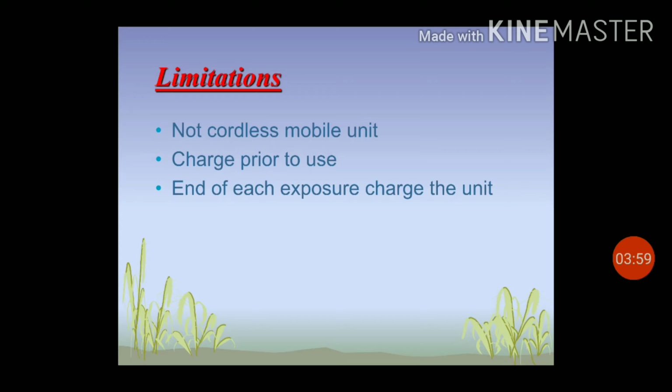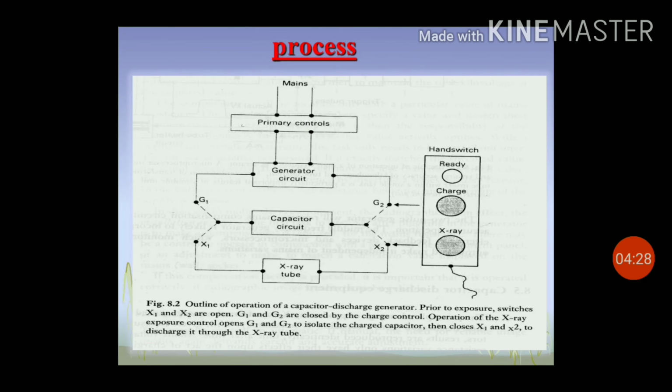Another limitation: capacitor discharge units are not cordless mobile units. The capacitor must be charged prior to its use, and we cannot charge the unit in the X-ray department and then take it anywhere in the hospital, because charge rapidly leaks from the capacitor. At the end of each exposure, the capacitor must be charged again. Some units do the charging automatically.